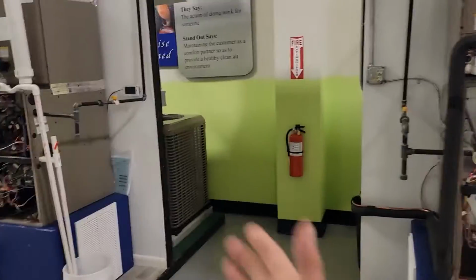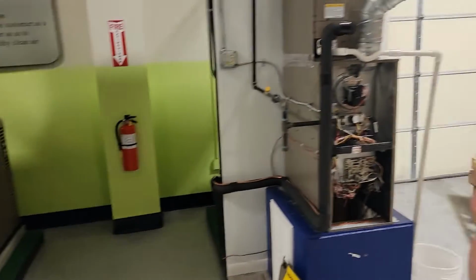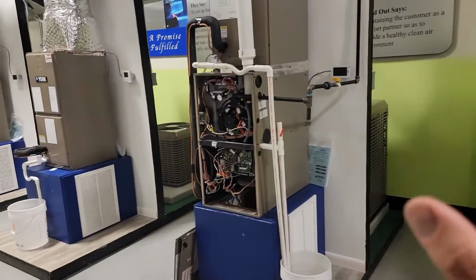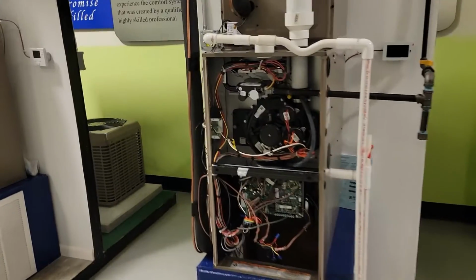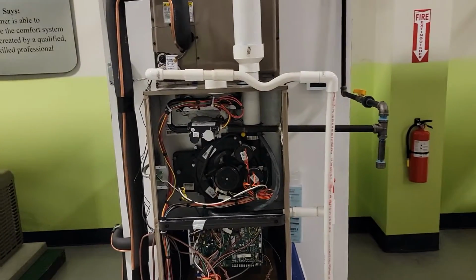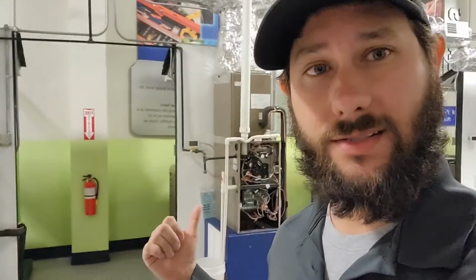And of course, when you look at price, this 90% furnace is going to be a little more expensive. But anytime you're using propane, this is definitely something that you need to do. You need to upgrade the customer's furnace, because propane is terrible. Propane is the worst fuel to use to heat your home, so you have to make it as efficient as possible, and a 90% furnace is a good way to minimize your waste of fuel. Also, coupling this 90% furnace with a heat pump, making it a dual fuel, takes it to an even more efficient level, which is a good idea.